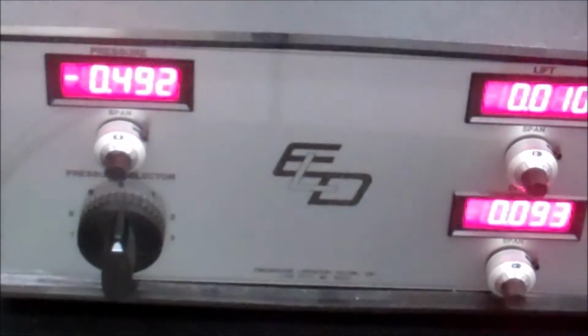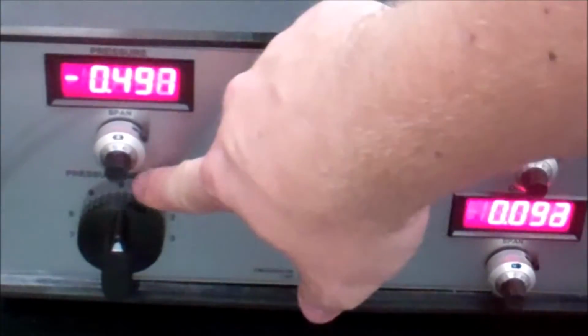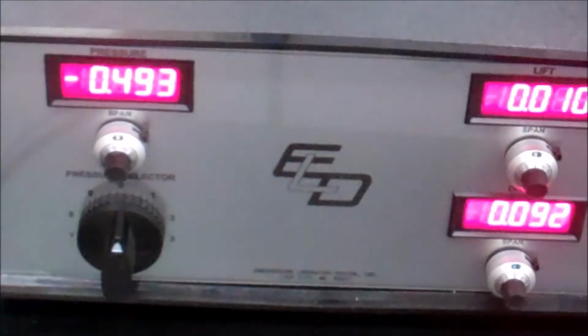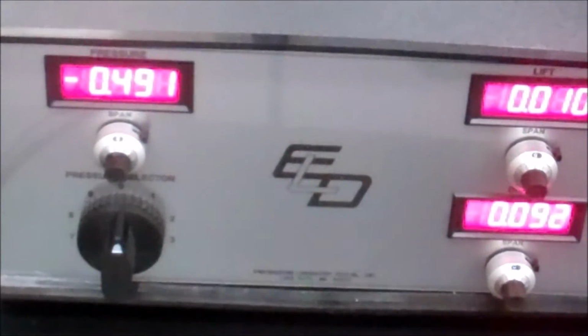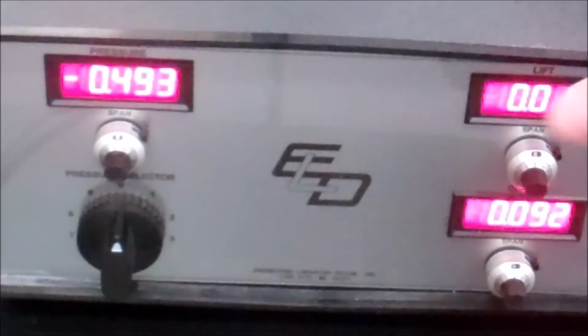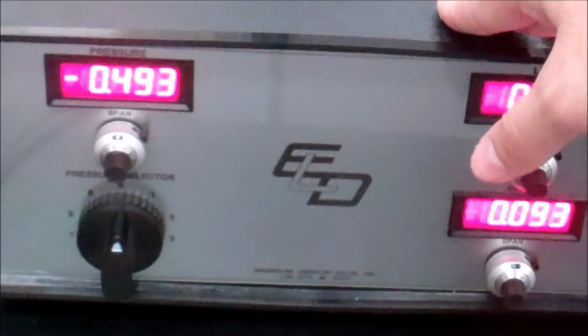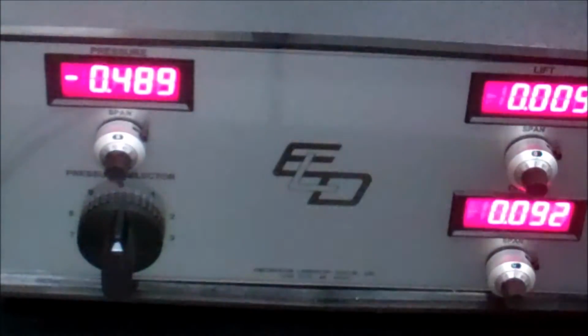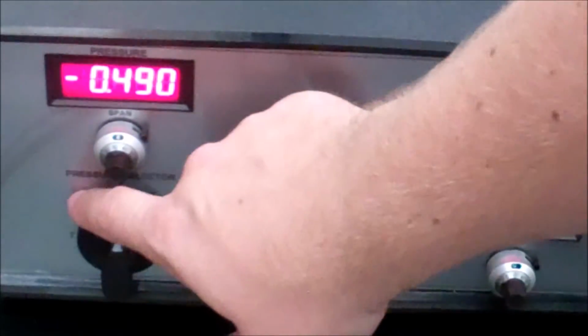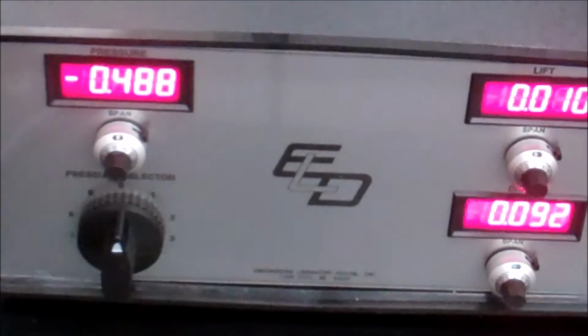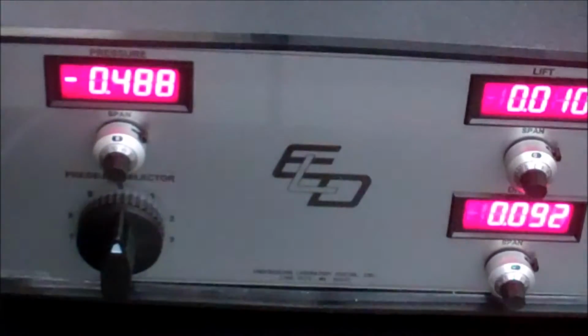Now once you let it sit for 15 minutes, you're going to want to zero out that voltage. So when you calibrate it, make sure this selector is at 0, because 0 corresponds to that total and static port. So if you hook up the pitot-static tube to this system with the total and static port, switch it to 0, you'll get the reading from the pitot-static tube. If you switch it to 1, 2, 3, 4, 5, 6, 7, 8, 9, that's going to read the pressure coming from this connector and these lines, whatever's connected to it.